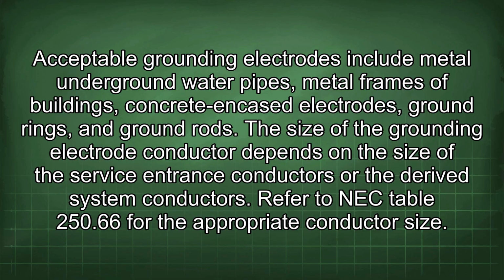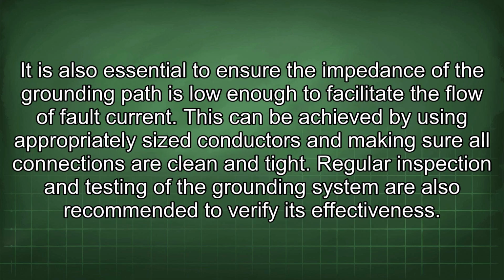The size of the grounding electrode conductor depends on the size of the service entrance conductors or the derived system conductors. Refer to NEC Table 250.66 for the appropriate conductor size. It is also essential to ensure the impedance of the grounding path is low enough to facilitate the flow of fault current. This can be achieved by using appropriately sized conductors and making sure all connections are clean and tight.